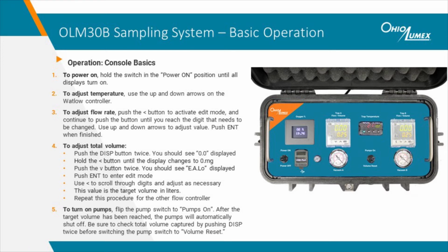You can also adjust the total volume the sampler will pull. Every time you turn off the pumps, the volume totalizer is reset to 0, and when you turn the pumps on, they will stay on until the target volume is reached. To adjust the target volume, first push the display button twice. You should see a 0.0 displayed.